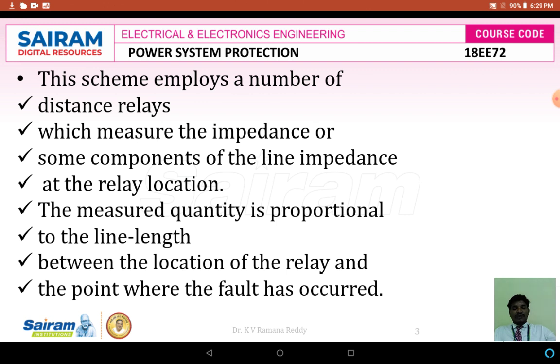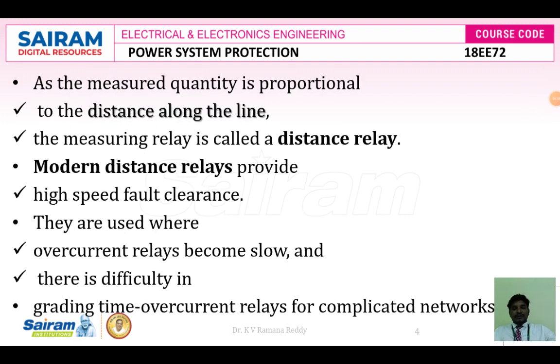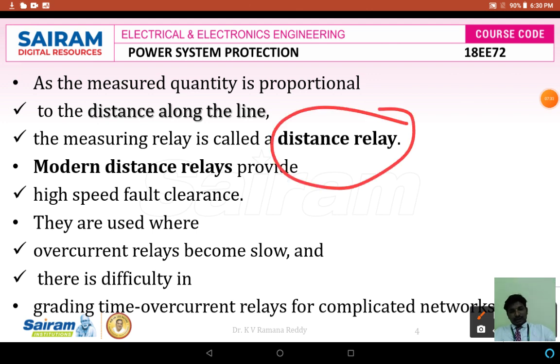Since the measured quantity is proportional to the distance along the line, the measuring relay is simply called a distance relay. Modern distance relays provide high-speed fault clearance. They are used where overcurrent relays become slow and where there is difficulty in grading time overcurrent relays for complicated networks. For complicated networks, it is difficult to identify which kind of overcurrent relay is suitable, and in such cases we can use the distance relay.